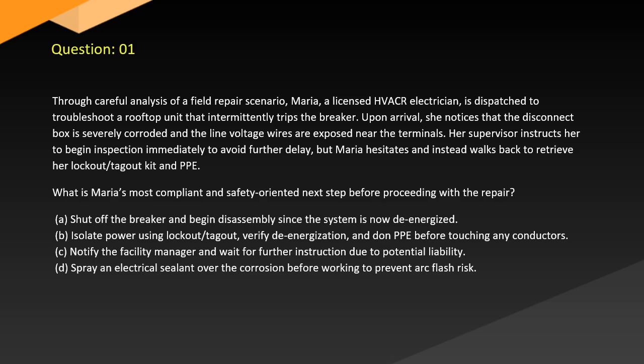What is Maria's most compliant and safety-oriented next step before proceeding with the repair? A. Shut off the breaker and begin disassembly since the system is now de-energized. B. Isolate power using lockout. Verify de-energization and DIEP before touching any conductors. C. Notify the facility manager and wait for further instruction due to potential liability. D. Spray an electrical sealant over the corrosion before working to prevent arc flash risk.